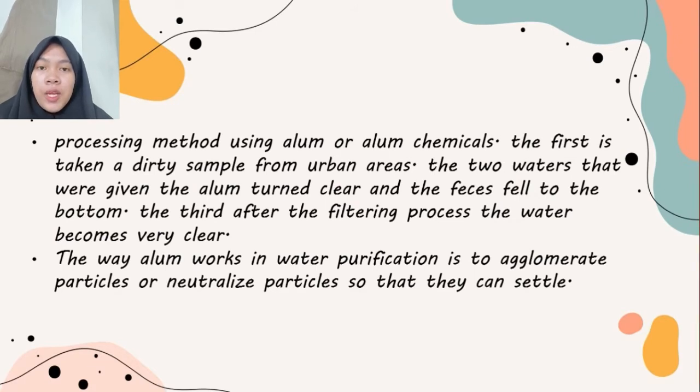With the presence of alum, it becomes attractive and can form layers or double layers, meaning that the first layer is attracted and the second layer is attracted, so that over time it becomes thick and rough and then it will settle.